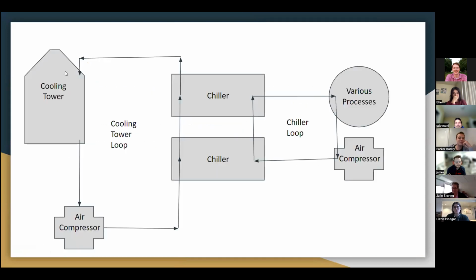Here we go. Background information. I think it's going to be easier if we start with this process flow, so everybody can understand what we're thinking with this AR. Trey was in charge of this process flow, and he'll describe what's happening here. I'll jump in because this is definitely a part that I had to have Connor draw me like 4 or 5 times so I could understand that there were 2 different loops. So basically, we'll start at the cooling tower. We have the cooling tower that is connected to one of the air compressors that cools one of them, and then also cools both the chillers, and then recycles it back in, cools the water, does that loop.